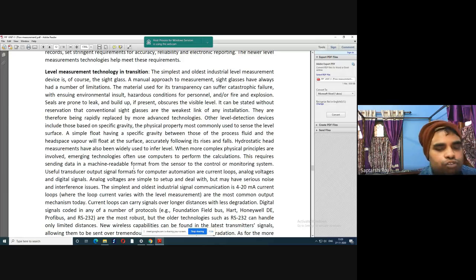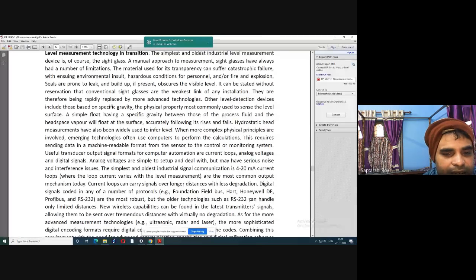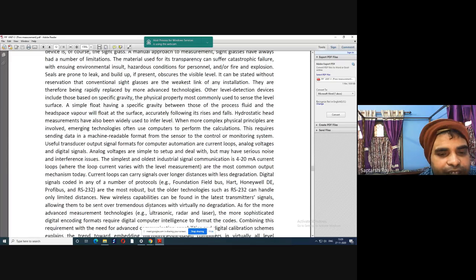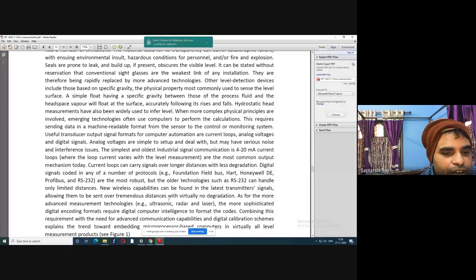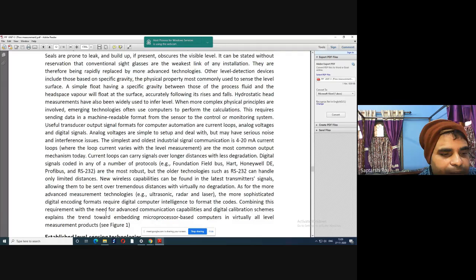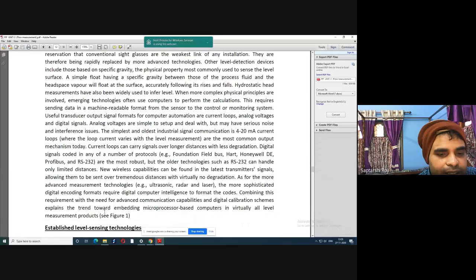These are the most common robust protocols, but older technologies such as RS-232 can handle only limited distances. New wireless capabilities can be found in the latest transmitters, allowing signals to be sent over tremendous distances with virtually no degradation. The more advanced measurement technologies, like ultrasonic, radar and laser, and the most sophisticated digital encoding formats require digital computer intelligence to format the codes. Combining this requirement with the need for advanced communication capabilities and digital calibration schemes explains the trend towards embedding microprocessor-based computers in virtually all level measurement products. See figure 1.